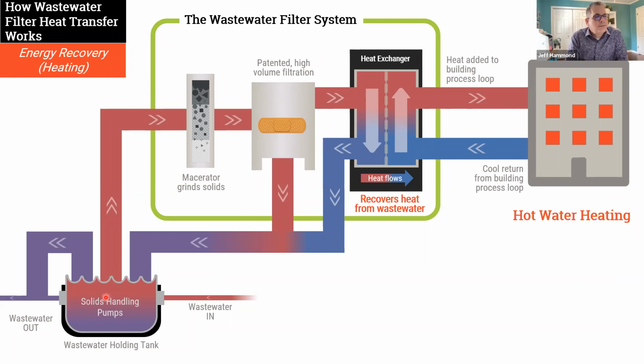Gary asks what the winter average temperature of wastewater is in northern cities such as Chicago. I don't know specifically about Chicago, but in Vancouver, BC we have a project called the False Creek Neighborhood Energy Utility, a district energy plant that takes its primary source for a wastewater source heat pump from a city sanitary main. Converting from Celsius to Fahrenheit, we typically see around 65 to about 80 degrees across the seasons, on the low and high end for winter and summer respectively. Other areas will see slight variations, and it may depend on whether they have combined sanitary and storm sewer systems, which could be affected by rainfall and snowmelt. It's best to look at your specific area.